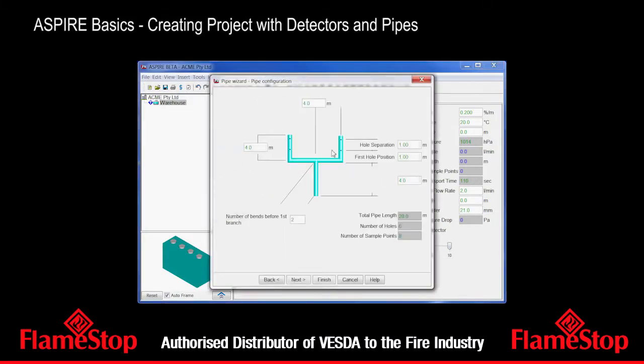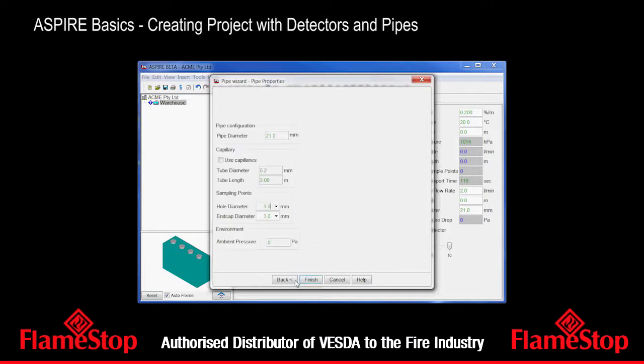Let's add a simple branch. We've given a whole lot of basic definitions. We're going to make this one 20 metres long. You'll notice when we did that, the number of holes increased. The number of sample points is the number of holes plus the two end caps, because the end caps also act as sample points. The first hole position — we're happy with all that. We can go to the other screen to set default hole sizes — that's probably the main thing to set there.